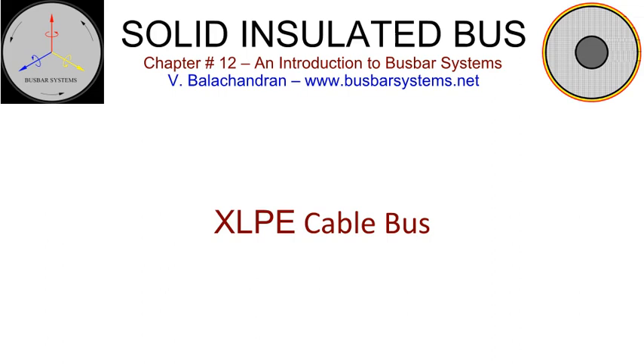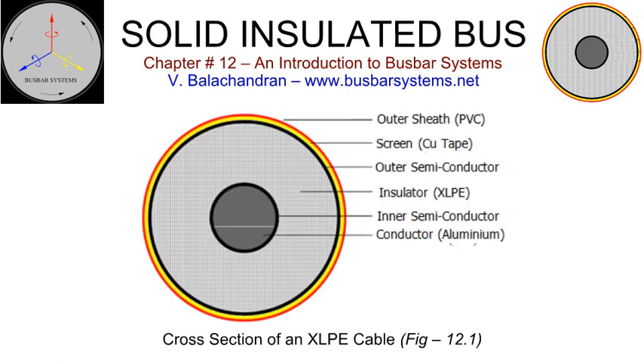XLPE cables are manufactured with copper or aluminium conductors. Single-core XLPE cables with copper conductors are manufactured up to 2,500 mm², with an approximate ampacity of 2,500 amperes in air and 2,000 amperes when buried or run in trenches. XLPE cable connections require clamps and terminating accessories. These are specific to the cable's size, rating, and construction of the cable. Terminating accessories will also depend upon the terminal arrangement of the connected equipment and its location, indoor, outdoor.